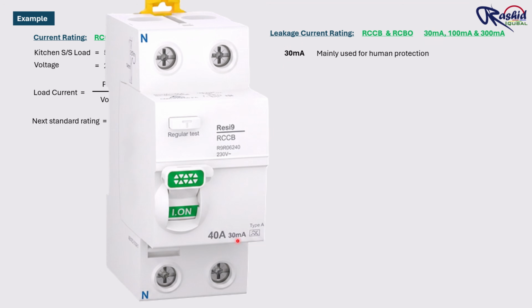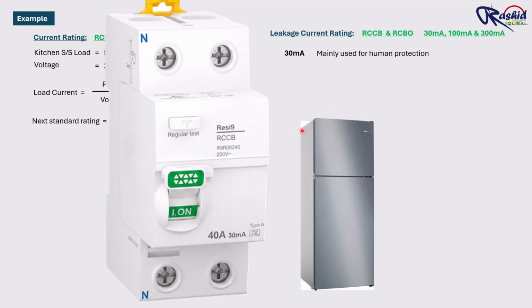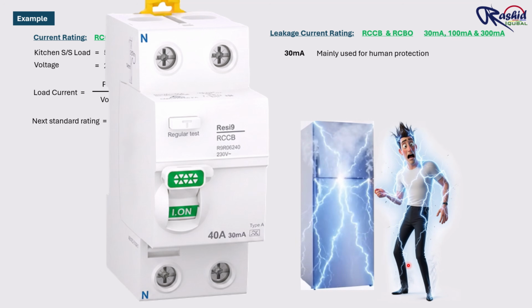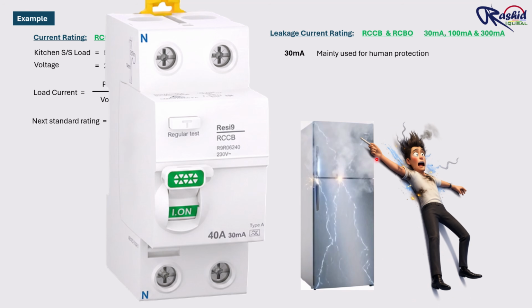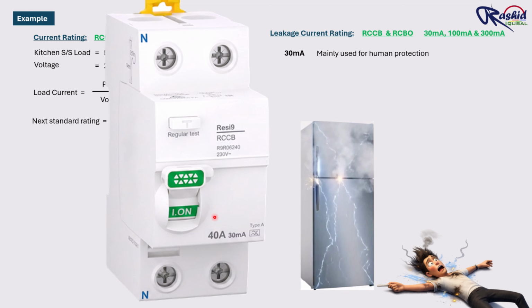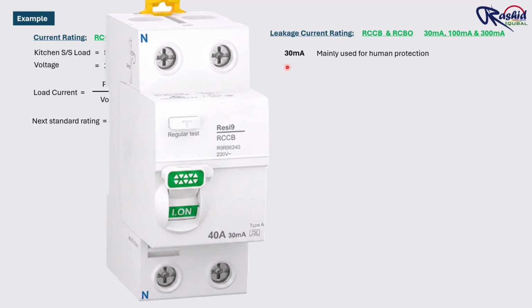The reason is that when electric current passes through the human body, it can affect the muscles, breathing and even the heart. So according to electrical safety standards, leakage current around 30 mA can become dangerous if it flows through the body for enough time. Therefore, a 30 mA RCCB is designed to detect this small leakage current and disconnect the supply very quickly. That is why 30 mA RCCBs or RCBOs are commonly installed on socket outlets, bathrooms, kitchens, outdoor circuits and other final circuits where people may come in direct contact with electrical equipment.